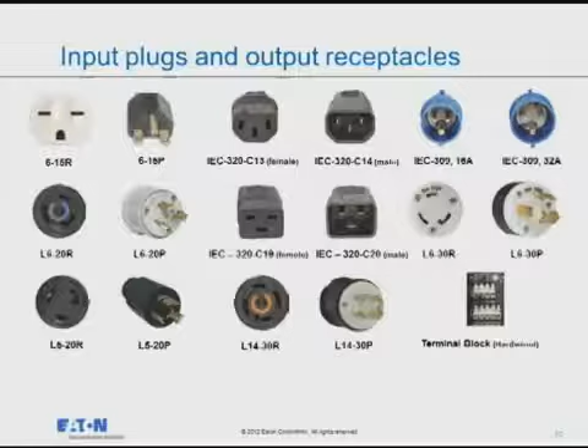Small single-phase UPSs, you're going to have receptacles on the back. So if you need different receptacles, we have to switch to a different model or a different type. Larger systems, typically 10 kilowatts to 20 kilowatts, you're going to have a doghouse or a distribution panel on the back of the UPS. And in that distribution panel, we insert the receptacles required. You're going to have, very similar to the equipment, a checklist saying how many of these do you want, and you buy them a la carte, if you will, and you embed them in there.